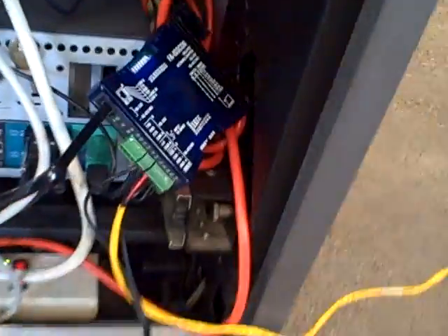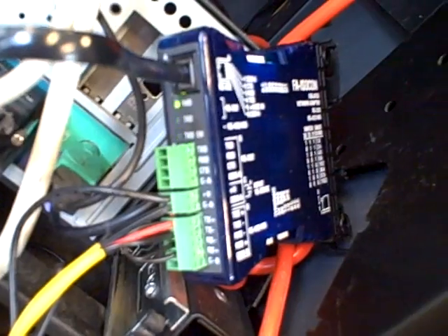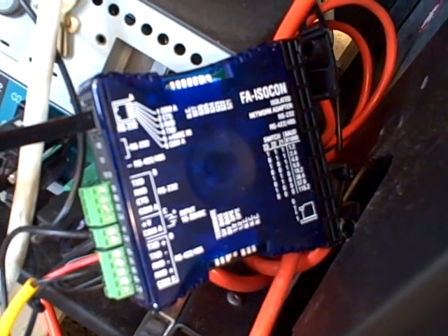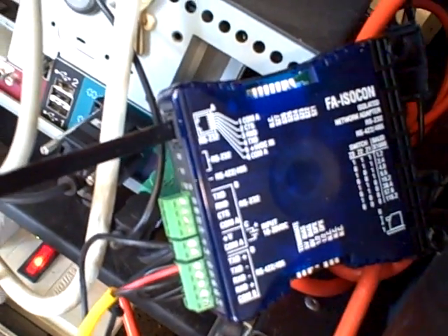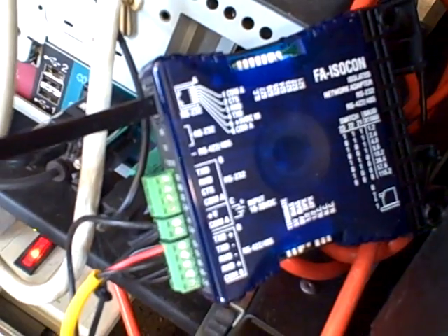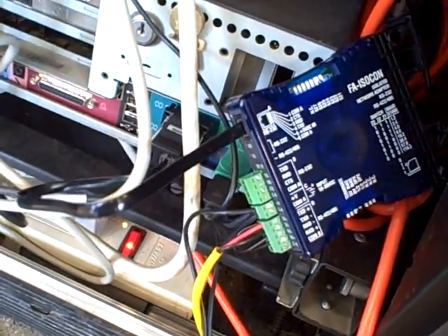Now to take a look at the network itself, this is very, very messy because we literally threw this together in one hour. At the back of the computer, we're coming out of a serial port to a converter. This particular converter takes the RS-232 pulses and converts that to RS-485 voltage pulses. So this is strictly a layer one converter, from layer one of RS-232 to layer one of RS-485. The actual data formatting is Modbus, but that's a layer seven standard, so this converter really has nothing to do with that. It's simply converting voltage signals.